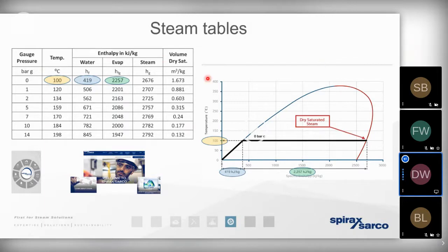So over towards the right-hand side of the screen, you can see what we refer to as the temperature enthalpy curve. And this demonstrates the journey that water takes as it changes state from a liquid to steam as a gas. So if we use the example of zero bar gauge, we know that water boils at 100 degrees. If we multiply that 100 by the 4.19 kilojoules per kilogram sensible heat, the water is going to boil once we've added 419 kilojoules of energy to it. But that boiling water is only going to fully evaporate once we've added that latent heat energy to it. And it's at this point we can say that we've got dry saturated steam.